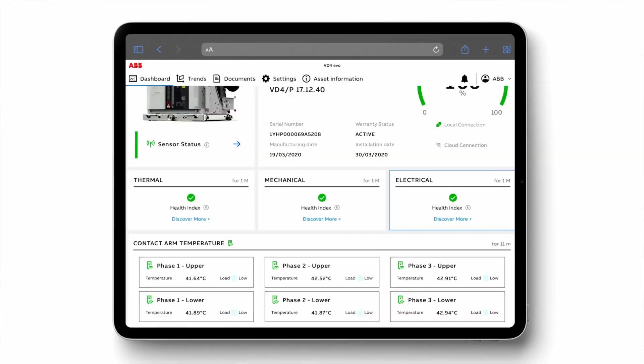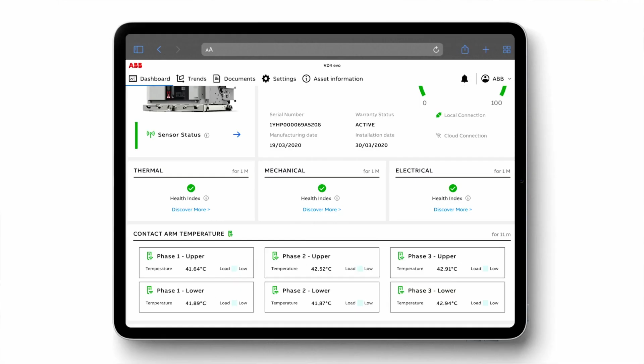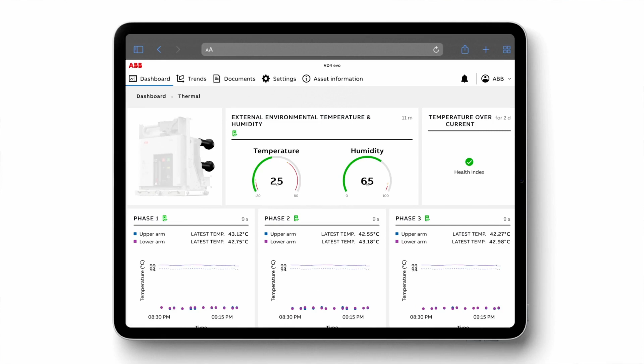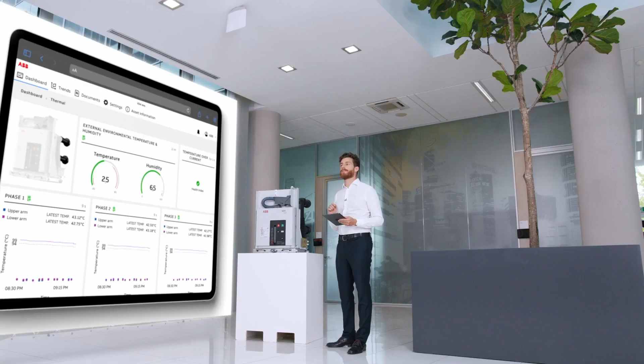So here I can see the key health indexes for the three areas we mentioned earlier: thermal, mechanical, and electrical static. If I see any abnormal parameters or get a warning message, I can easily navigate further in the dashboard. For example, the thermal page is where I would go if a loose joint or a damaged contact resulted in abnormal temperature profiles in one or more phases.